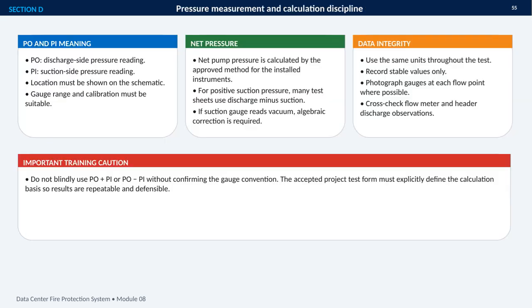that needs follow-up. This section focuses on pressure measurement and the discipline required to calculate and document results correctly. PO refers to the discharge side pressure reading, while PI refers to the suction side reading. The gauge locations must be clearly identified on the schematic, and each gauge must have a suitable range and current calibration. Net pump pressure is not calculated by a universal rule. The approved method depends on the instruments installed and the gauge convention being used. When suction pressure is positive, test sheets commonly calculate net pressure as discharge pressure minus suction pressure. But if the suction gauge indicates vacuum, an algebraic correction is required.